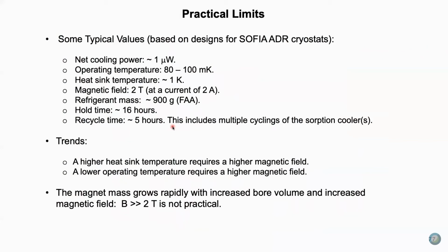Here are some practical limits for ADRs based on designs for SOFIA. Net cooling power, about a microwatt. So this is after you've subtracted off the parasitics from the gross cooling power. Operating temperature, 80 to 100 millikelvin by design. HAWC operated quite a bit warmer than that, up around 180. Heat sink temperature, around 1 Kelvin, which can be provided by a helium-4 sorption refrigerator. Magnetic field, 2 Tesla at a current of 2 amps. Refrigerant mass, about 900 grams of FAA, and a hold time of 16 hours, a recycle time of 5 hours.